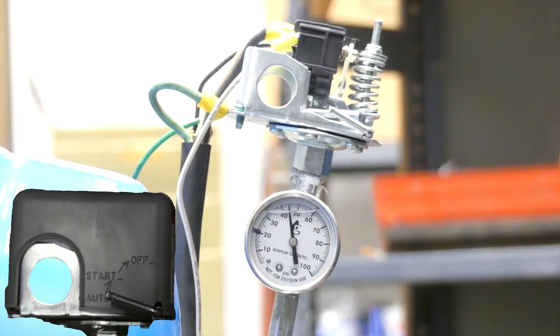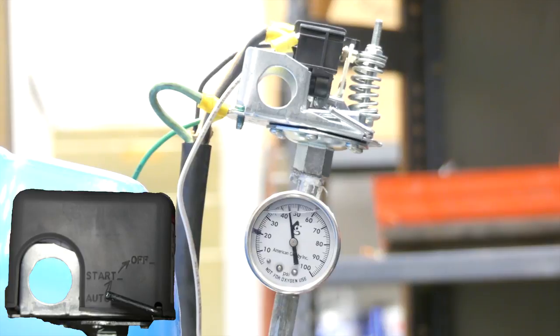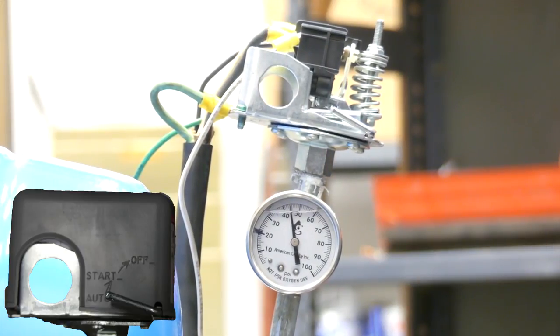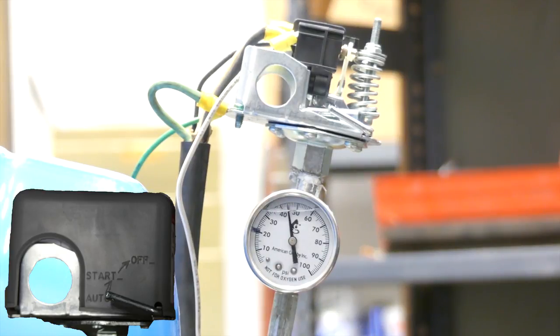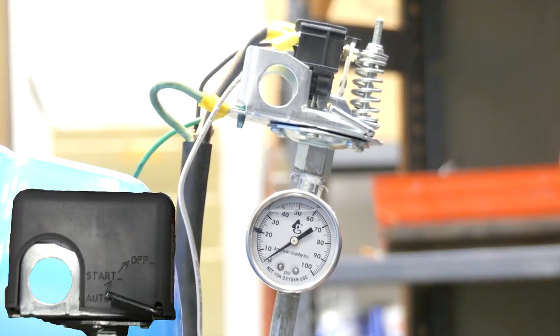Now let's say I'm going to open a valve over here and the system lost prime or the well ran out of water. I can hear that water running out, and hopefully that'll be enough to cause this thing some grief. We finally got the pump to lose all of its prime. As we can see, we're at dead zero and this pump is not calling for water.